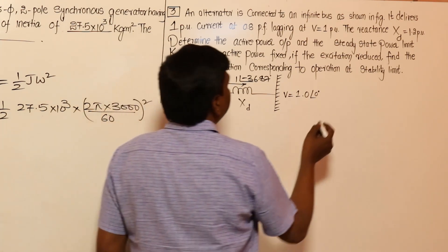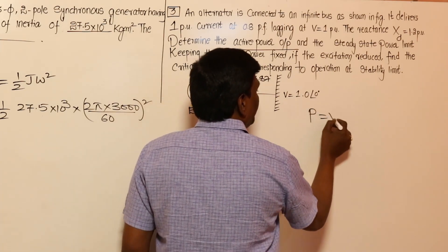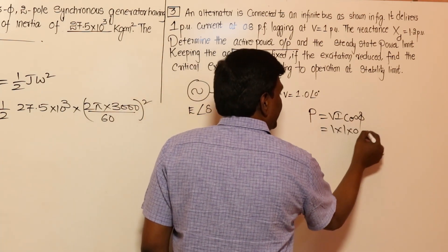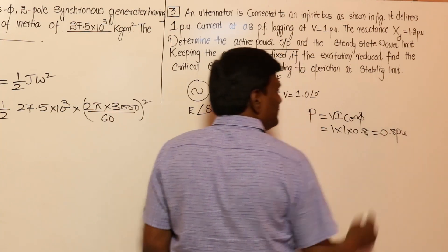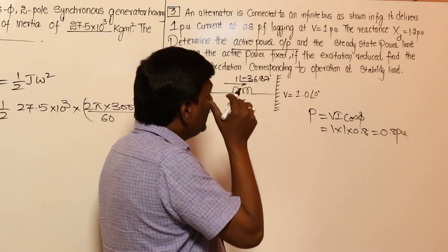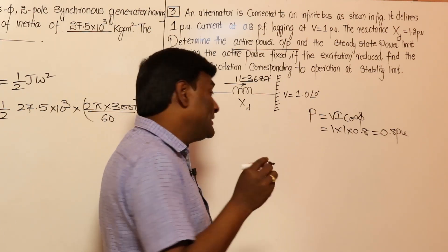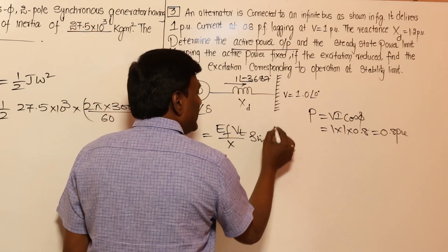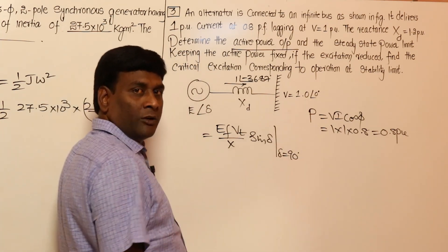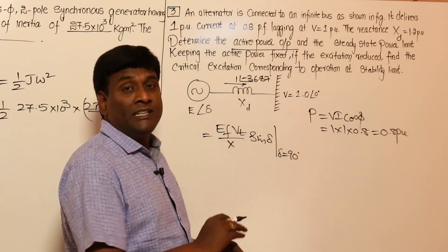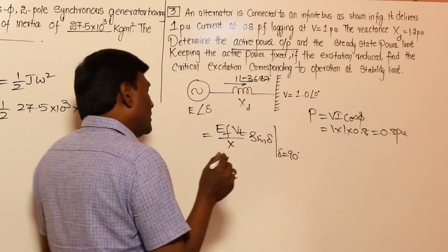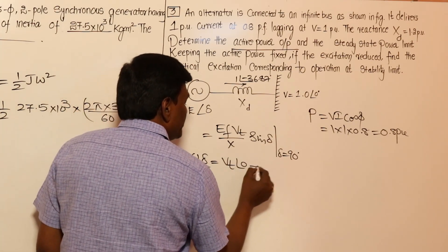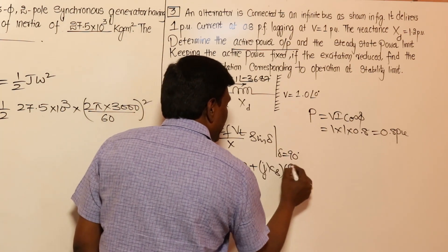First, active power output P = V×I×cos(φ) = 1×1×0.8 = 0.8 per unit. Next, steady state power limit = E_F×V_T / X at δ = 90°, which equals E_F×V_T / X. So we need to calculate E_F. Using E_F∠δ = V_T∠0 + j×X_S × I_A∠φ, this gives 1∠0 + j×1.2 × 1∠(−36.87°).